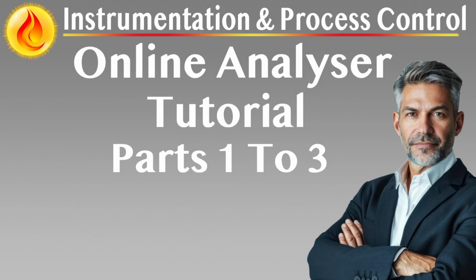Analyzer houses are essential for ensuring the continuous, reliable operation of online analyzer systems by offering a controlled and protected environment. These buildings shield sensitive instrumentation from environmental hazards such as extreme temperatures, high humidity, dust, and corrosive sulfurous air. The quality and stability of the analyzer environment directly affect the performance, calibration stability, and lifespan of the instruments housed within. Their construction should only be considered where operational needs cannot be satisfied by simpler solutions, such as walk-in shelters.